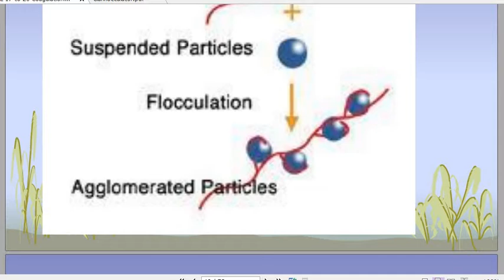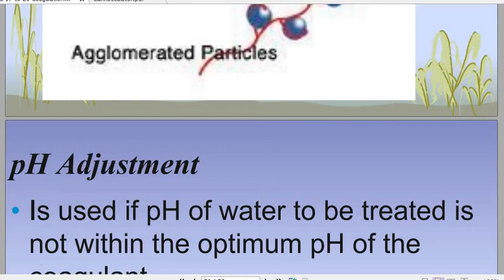Also, the use of polyelectrolytes not only broadens the pH range over which satisfactory flocculation could occur, but it may also reduce the quantity of primary coagulant required. Generally, the dose of the polyelectrolytes required after the addition of coagulant is about 1 ppm. So after addition of coagulant aids, it will reduce the optimum dose of coagulant, and hence it will accelerate the coagulation and flocculation process.